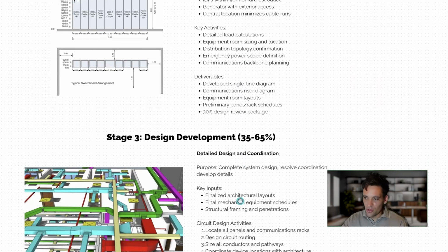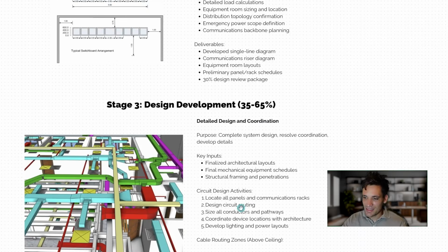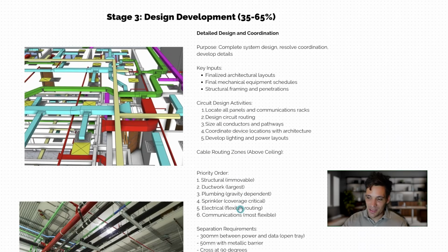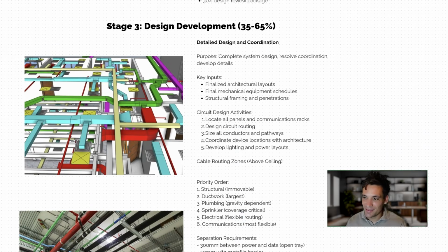Once we've got all our loads, we've finalized the system architecture, we've got the single line diagram, well, not the exact one, but we've got the single line diagram. Now is the time to fully flesh out our design to work out where every single exact load is going to go. We know exactly what these loads are. We're going to start routing the cables and work out where all the cables are going, because we know the load, source, and the distance of the cable.